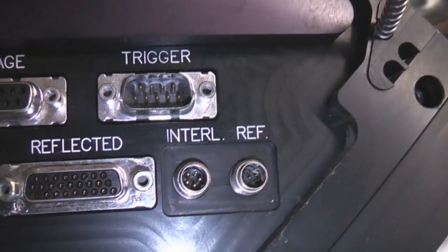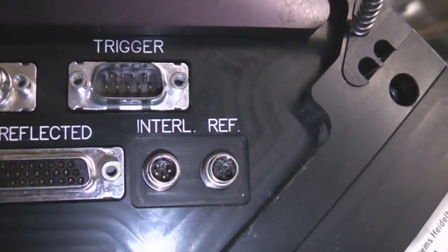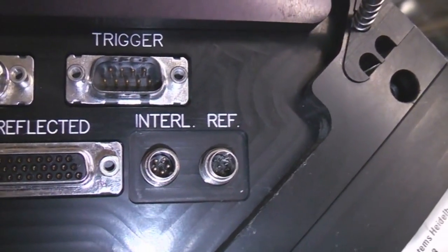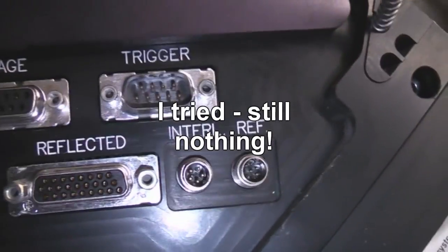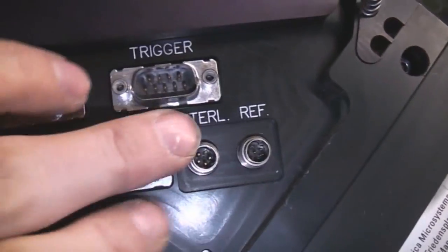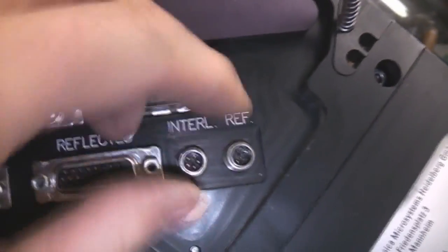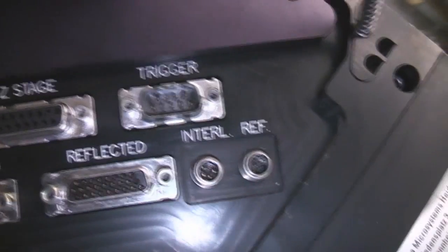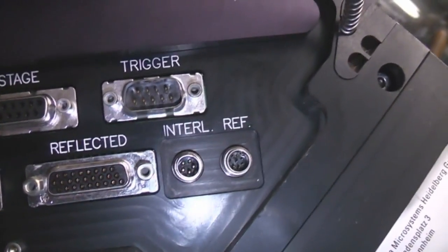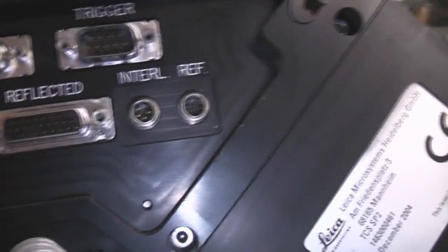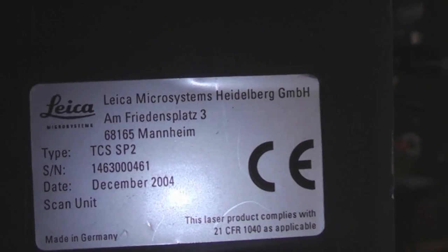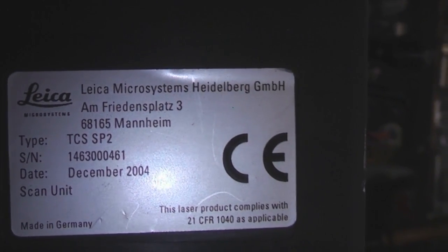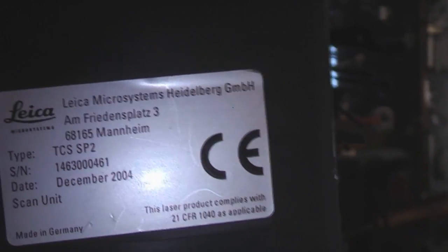I just noticed there's, I'm assuming that's interlock now. I wonder if that might be the reason I couldn't get anything to turn on. Assuming it's the same connector as this interlock connector here, I might see if I can put a plug in that, because it may well be that there's a plug from the microscope body that goes on here, so that when you detach the two, that comes off so you don't get lasers sort of flying out of the open aperture. So it may be the case that that's just an additional interlock that's connected into the microscope to avoid any lasers leaking out. Here's the part number sticker, December 2004 manufacturing date, although I noticed a date of 2010 on the Argon Laser, so maybe that's been replaced at some point.